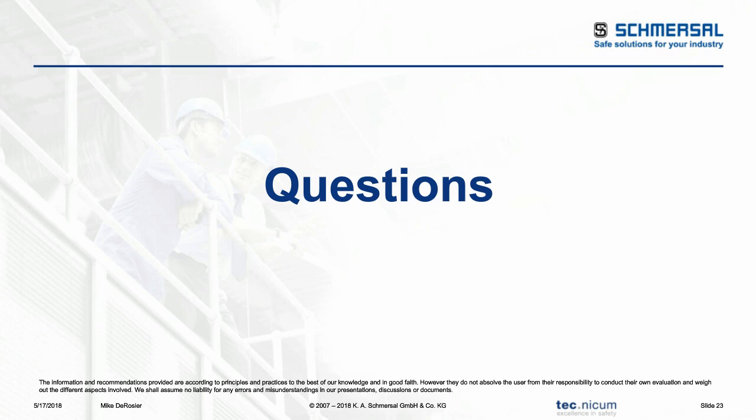Some of the reasons, and this actually has partly been addressed in one of the latest standards, ISO 14119, where they talk about the motivation of defeat of guarding. It might be that being outside the danger zone is because maybe there's solid sheet metal panels, or I just can't see how the machine's operating, so the guarding gets removed or somebody places themselves in there so they can see what's going on. How about adding some design characteristics such as visibility to getting in there? So there's certain things you can do. The next step you would do is, let's say you have to be in there. Follow the concept of what the robot industry has done.